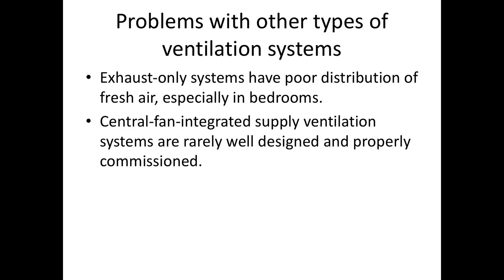Central fan integrated supply ventilation systems, the type that introduces a little exterior air into your return air plenum, are rarely well designed and properly commissioned. The theory is great, and when Building Science Corporation installs them, they work perfectly, and they're the least expensive type of ventilation system that provides good air distribution. The trouble is the only way they work well is if somebody measures airflow, and we can't find HVAC contractors who measure airflow. I guess it could be argued that's a problem with all ventilation systems. It's less of a problem with an ERV or an HRV because there's better instructions from them, and the devices themselves have a way of addressing overventilation and underventilation in a way that these outdoor air ducts don't.